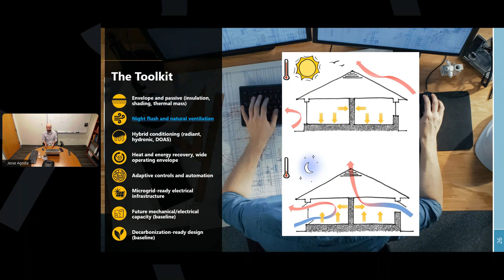This strategy relies on shifting the peak condition that the building sees. So on our next slide, where we talk about hybrid conditioning, it includes radiant floors with hydronic piping tied to a dedicated outside air system, or DOAS. This amplifies the night flush and natural ventilation strategy by improving the effectiveness of heat transfer at our thermal mass. So we're basically moving all of our heat transfer technology down to the floor or a radiant ceiling, where the sensible load of the space can be dealt with directly.